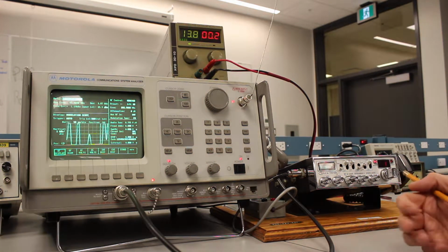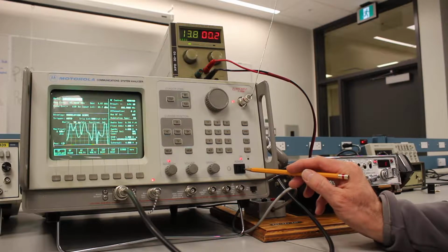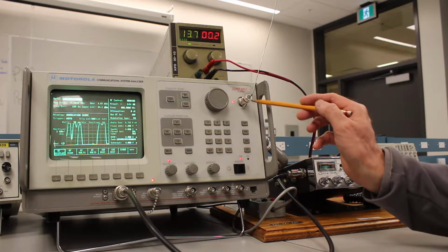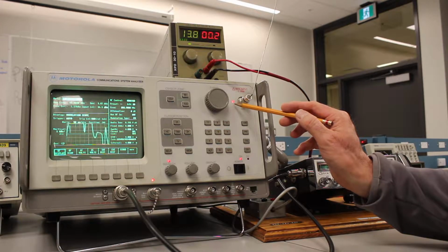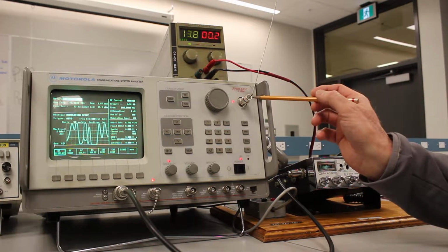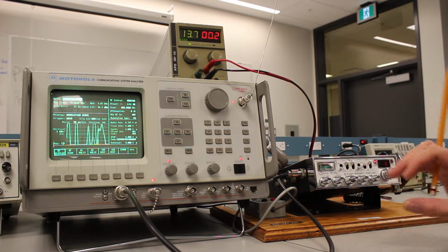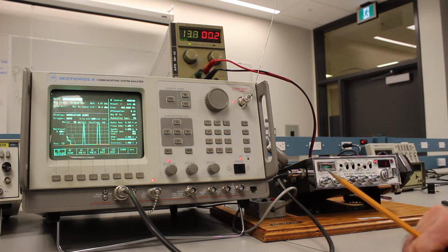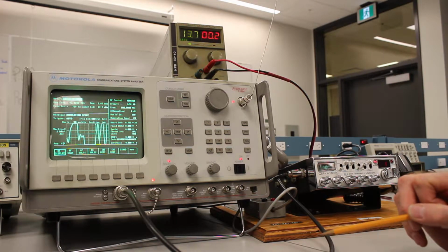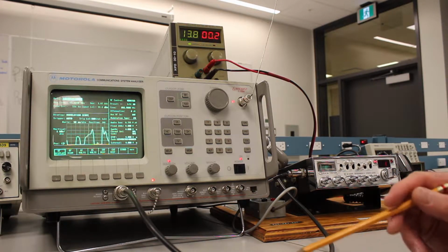When we power up the instrument from the toggle key at the bottom right hand corner, we will next want to put the antenna immediately into the antenna port. The red LED to the immediate left of it should illuminate. The purpose of putting that antenna on immediately is to mitigate any possibility of wrongly putting other connections to that particular port that could damage the instrument.